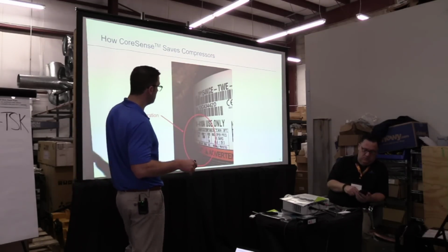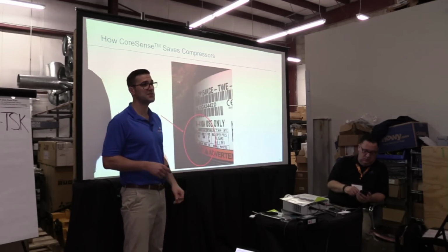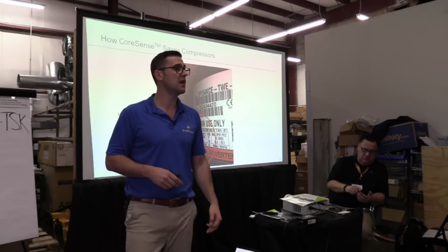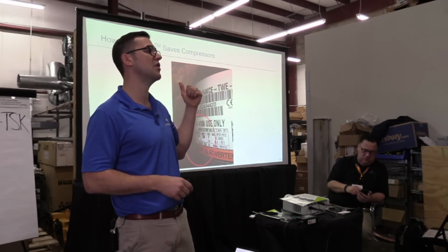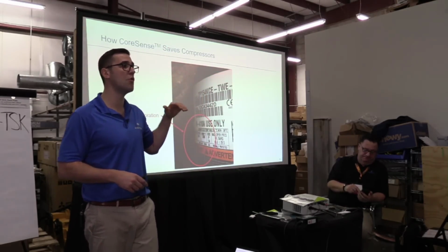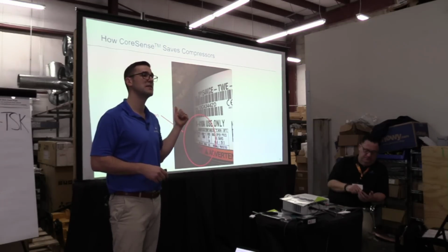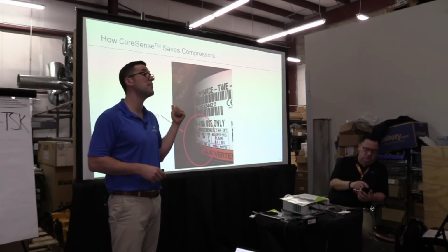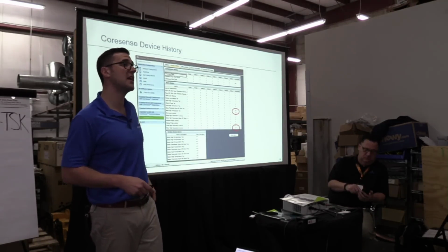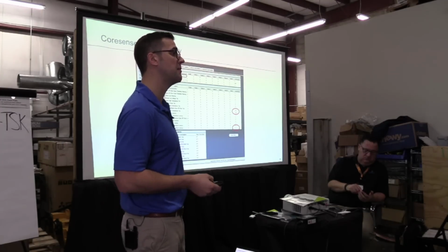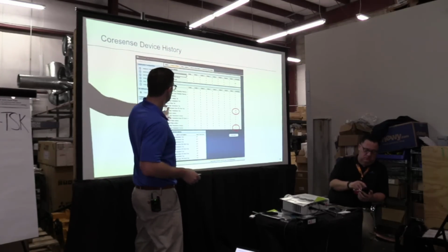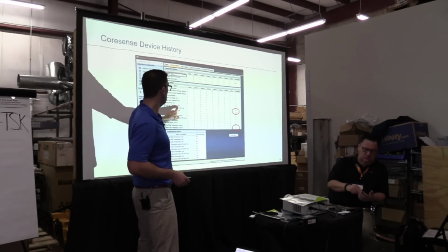I know it's hard to see, but I had to go to a job site for an OEM. The contractor was in there and said, oh, CoreSense is no good, it's terrible. My compressor won't run because of this CoreSense thing. I'm ripping it out. So they had it bypassed. When I went there, I took a look. The first thing is that I hooked up my module. Scroll high temp trip.